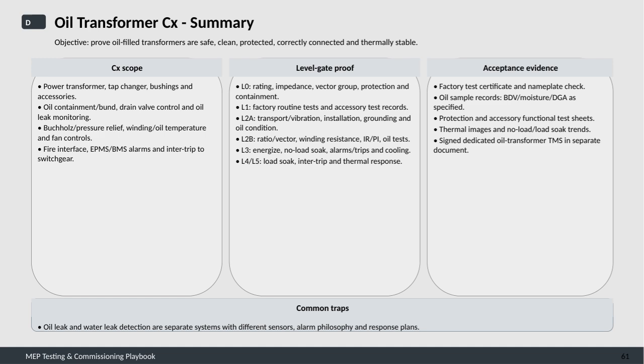Level 3 is about energizing the transformer, monitoring no-load soak conditions, alarms, trips, and cooling systems. Finally, Levels 4 and 5 focus on load soak testing, inter-trip operations, and thermal response verification. Acceptance evidence is a crucial part of this playbook.